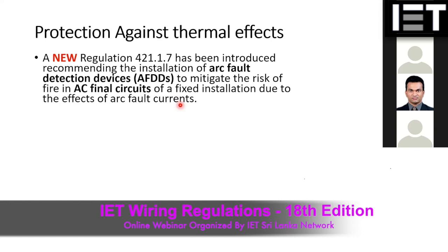When you look at the traditional way, we were talking about the MCB or overcurrent protection and the earth fault protection or RCD. That is the normal requirement with the equipotential bonding. But people realized that arc faults are not detected by any of this equipment. Because of that, new devices were introduced, arc fault detection devices, AFDD. That is for the final circuits. Now normally we know that if there is a live to neutral connection, a short circuit, that will be detected by the MCB as usual. That is the usual overcurrent protection. But the arc fault detection device also detects this type of fault.